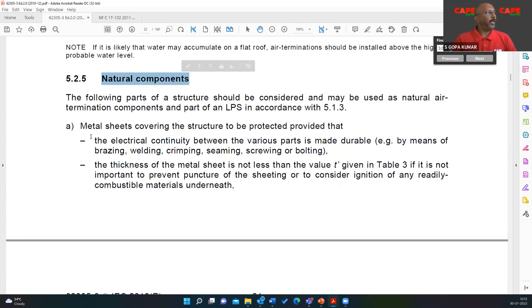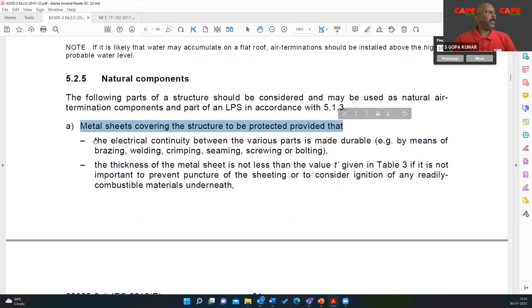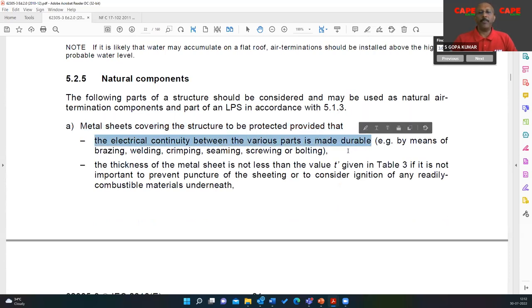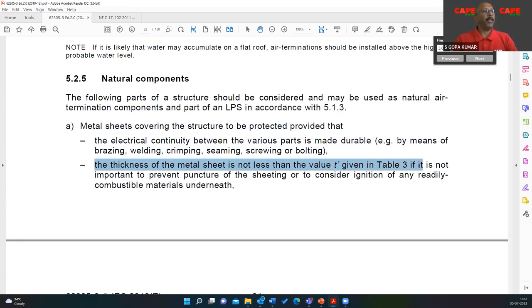There are two points here. The metal sheet covering the structure to be protected, provided the electrical continuity between various parts is made durable. We have to test and ensure that the continuity resistances are low.